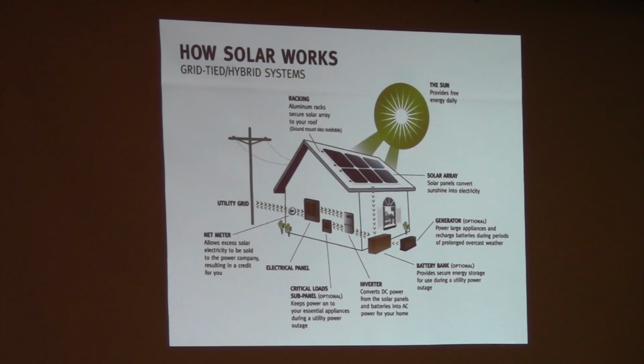What about motor starting loads? Are the inverters designed where you can start your air conditioner off of it? Yep. The newer inverter systems designed for home backup, which is most of what we do, have a huge capacitor bank with a large startup surge. Typically, they can sustain a load of 12,000 watts for 5 seconds for starting up large motors like an air conditioner compressor or a well pump.